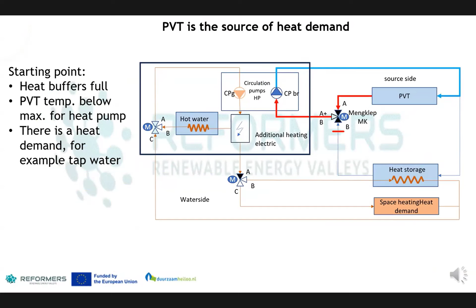However, it is possible that the temperature of the PVT is too high for the heat pump that cannot go higher than about 25 degrees Celsius. In that case, the PVT is shut down or the flow is diminished, and the PCM storage is supplying additional. That storage should therefore not exceed the maximum temperature that the heat pump can handle. In that case, both PVT and PCM are above the limits of the required temperature, and the heat pump will shut down. In this case, the input of the PVT is more or less closed, and the red line from the PCM storage goes to the heat pump, with the blue line back to the PCM tank, and partly the PVT. The set point of the mixing valve has to be set on the optimum temperature to the heat pump to get the best COP or efficiency of the heat pump.